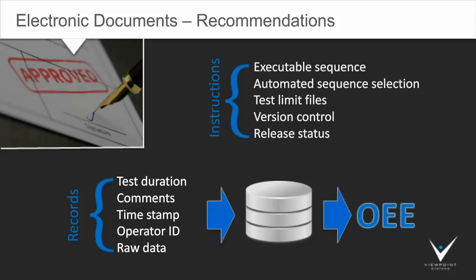Convert your instructions into electronic executable test sequences. Have the test application choose the test sequence automatically based on part ID or model number, rather than searching for appropriate paper documentation. Use test limit files based on the model and retrieve those automatically with the test sequence. Enhance your test applications to notice versions so that outdated versions are not used by mistake. And finally, enhance the test application to recognize the release status of the instructions so only qualified people are allowed appropriate access to the instructions.